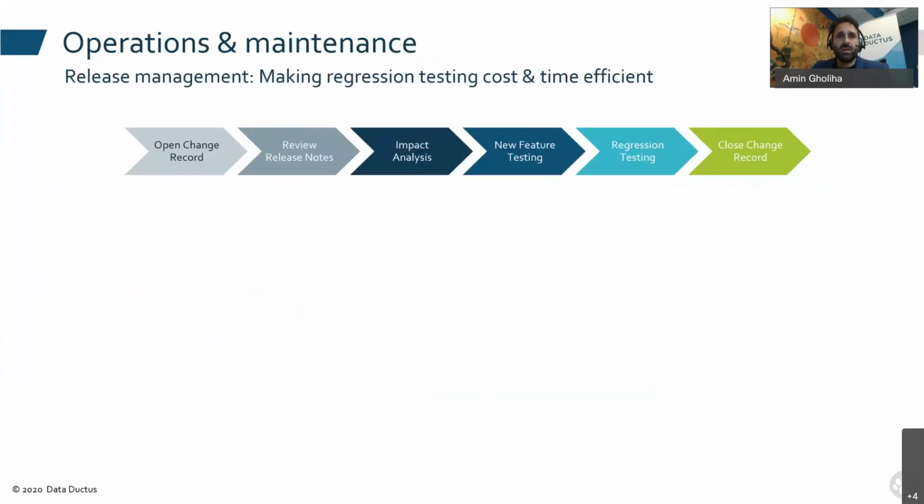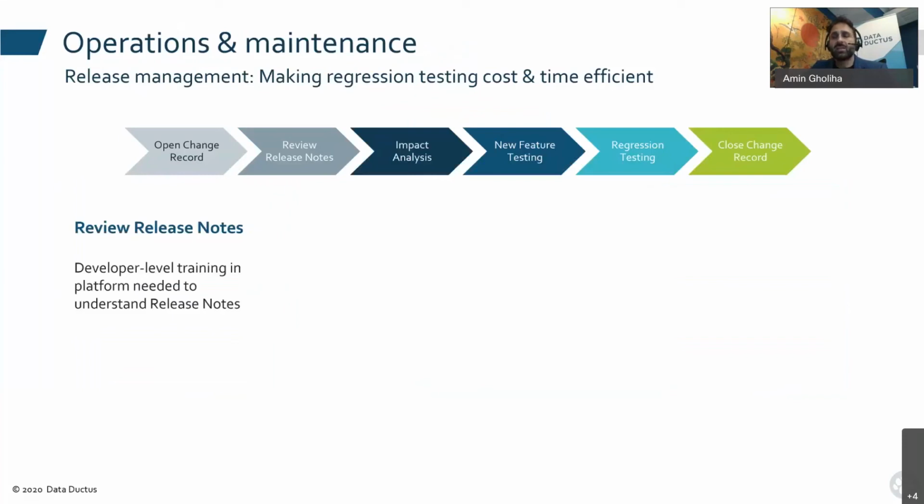So you need to have a process to be able to review release notes and really understand these complicated release notes, what it means and what impact it has for your validated system, basically. You need to make impact and risk analysis, and try and map it to your user requirements to see what parts maybe you need to revalidate and what part you need to test.